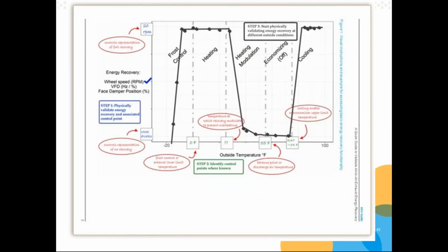The idea being, if they can do this, they can make this curve that I talked about early on, which basically just shows when energy recovery is on, when it's off, and we can compare that to some of the things we've learned. If the energy recovery system's working between 0 and 45 degrees, it's probably doing most of its job. And we would have to be really motivated to go after savings that are outside of that. So we'd be essentially really concerned about energy efficiency if we want to go from 80% to 100%. And we have that opportunity, and we will characterize it as long as we fundamentally understand when our system's on and off.